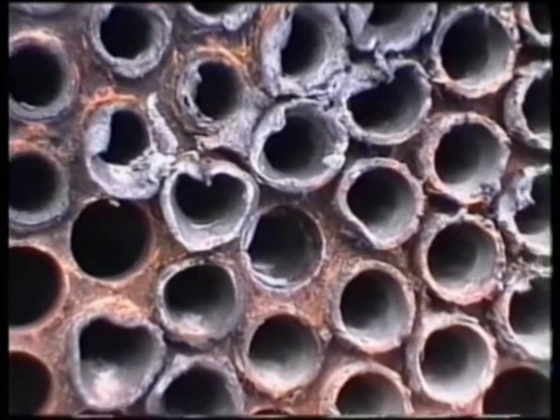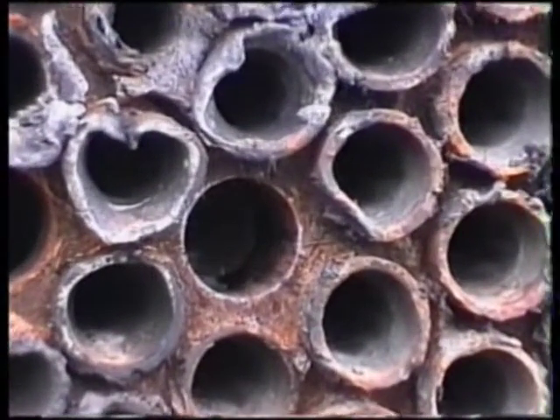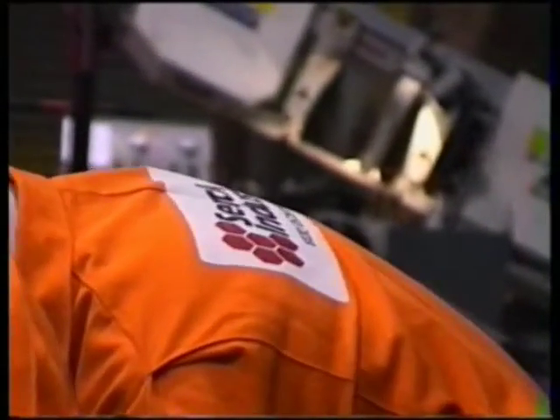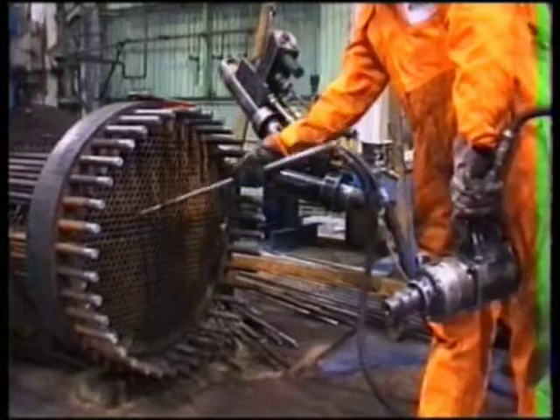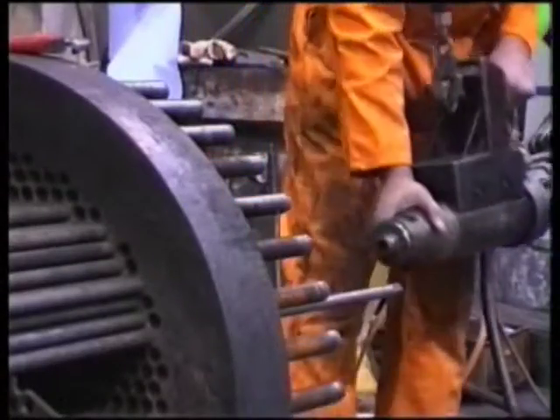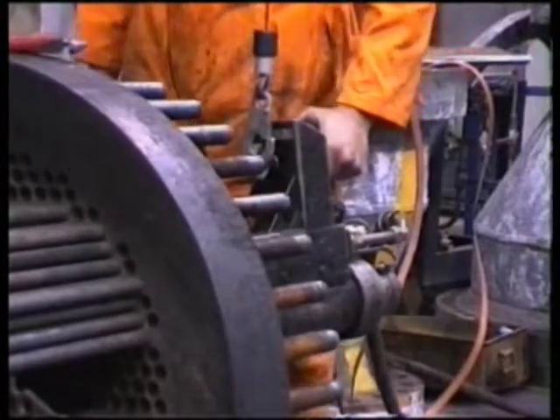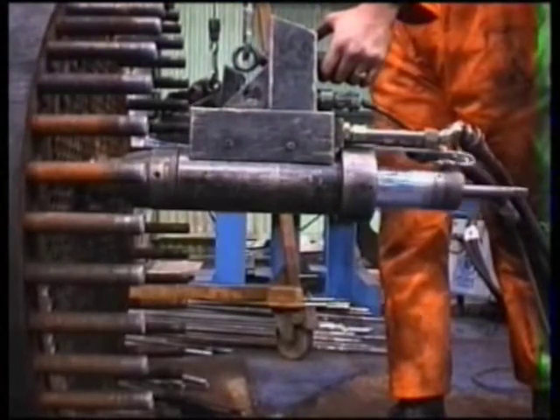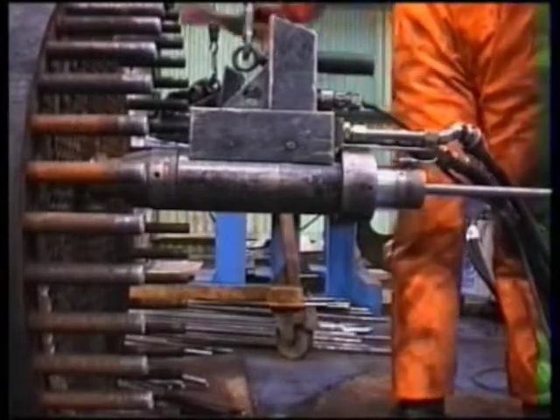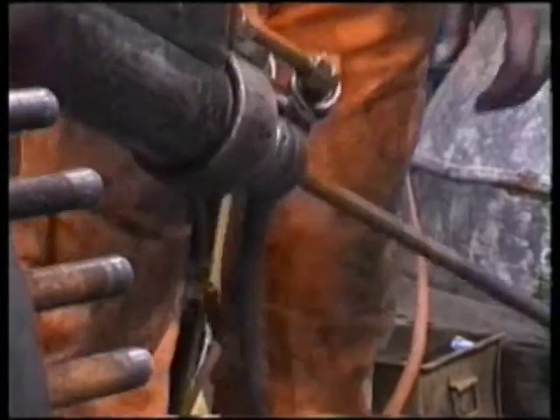For ease of use, the 15,000 couldn't be simpler. There is normally no need for tube cutting, thinning, or collapsing, and it pulls both front and back expansion in one simple action. Firstly, secure the extractor mandrel using an impacting wrench. Then load the gun onto the mandrel and slow start the pulling action under manual push-button control. Then start the auto-cycle by pushing the auto-cycling button and continue until the tube is free enough to pull out by hand or until the tube is fully extracted.